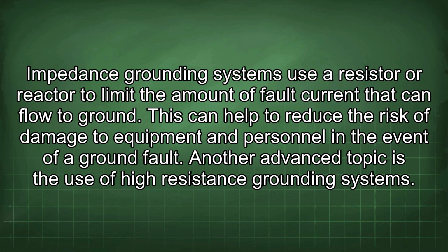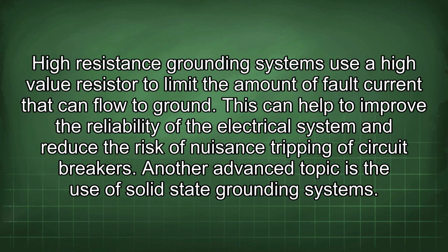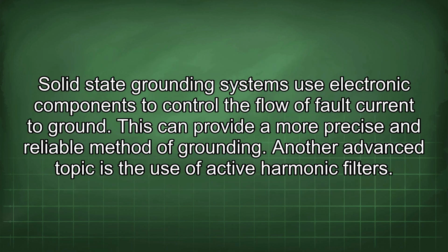Another advanced topic is the use of high-resistance grounding systems. High-resistance grounding systems use a high-value resistor to limit the amount of fault current that can flow to ground. This can help to improve the reliability of the electrical system and reduce the risk of nuisance tripping of circuit breakers. Another advanced topic is the use of solid-state grounding systems. Solid-state grounding systems use electronic components to control the flow of fault current to ground. This can provide a more precise and reliable method of grounding.